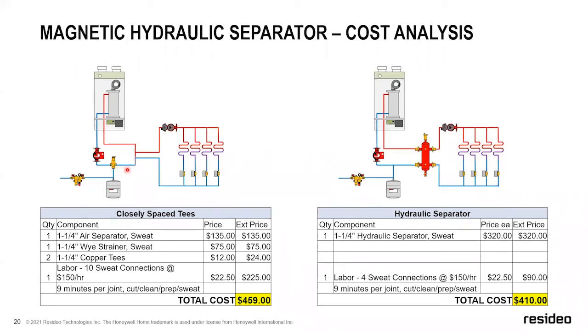I always encourage people to put in Y strainers, because I've seen large lumps of solder fall off into the system. So I've always suggested putting a Y strainer on the boiler return as well. Now we're talking 2 more connections, so we have a total of 10 different sweat connections in this example. And if you're using press, it'd be the same thing. I've worked with another trainer who gave me an average of 9 minutes per joint per 1.25 inch. If we've got any contractors in the line, I'm sure some of you will tell me you can do it faster, and some of you will tell me you're doing it slower. 9 minutes is the average I was given by a trainer that does a lot of plumbing trades and helps people build out their labor costs.